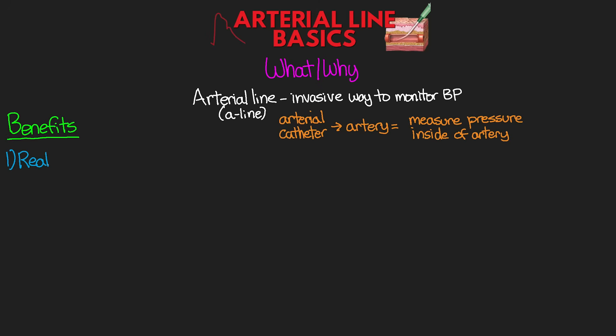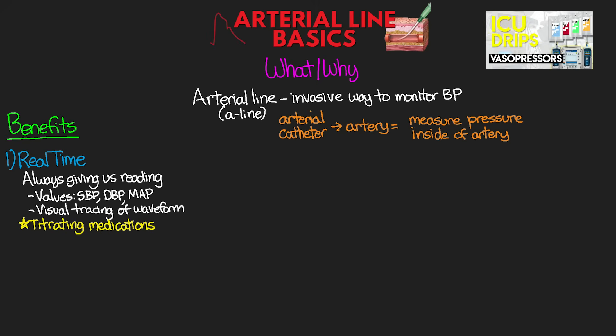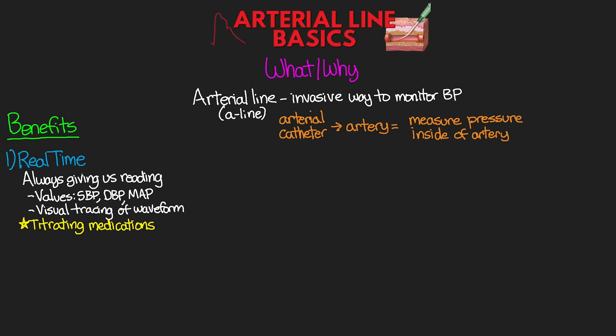The first benefit is real-time reading. The A-line is always giving us a reading, so at any moment in time we can get not only the values for our patient's systolic blood pressure, diastolic blood pressure, and mean pressure, but also a visual tracing of the pressure waveform. I am going to be covering this tracing in much more detail in the next lesson. One big advantage to having this real-time blood pressure is when it comes to titrating medications, particularly our vasoactive medications. You'll be able to adjust the medication at any moment as you'll know what your patient's blood pressure is, and you'll be able to see the effects in real time of their blood pressure changing either up or down.